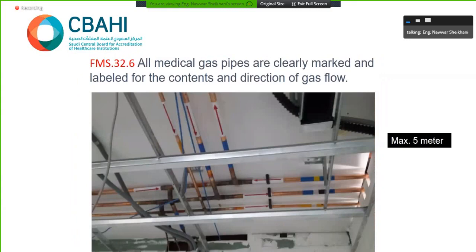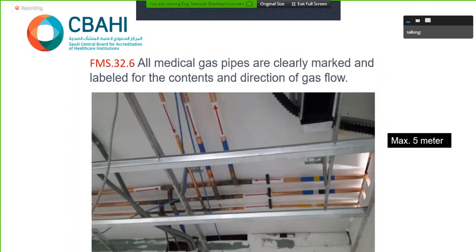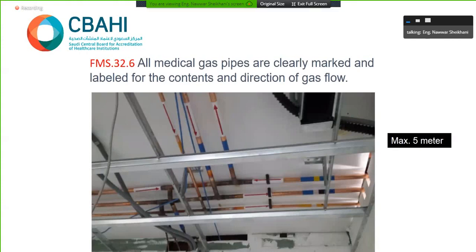All medical gas pipes are clearly marked and labeled, with the direction of gas flow, like this one. A frequent question is how frequent the labels should be. Actually, it's from 3 to 5 meters, maximum 5 meters. This is to allow the technician to recognize the pipe, whether it's oxygen or nitrous oxide or whatever.